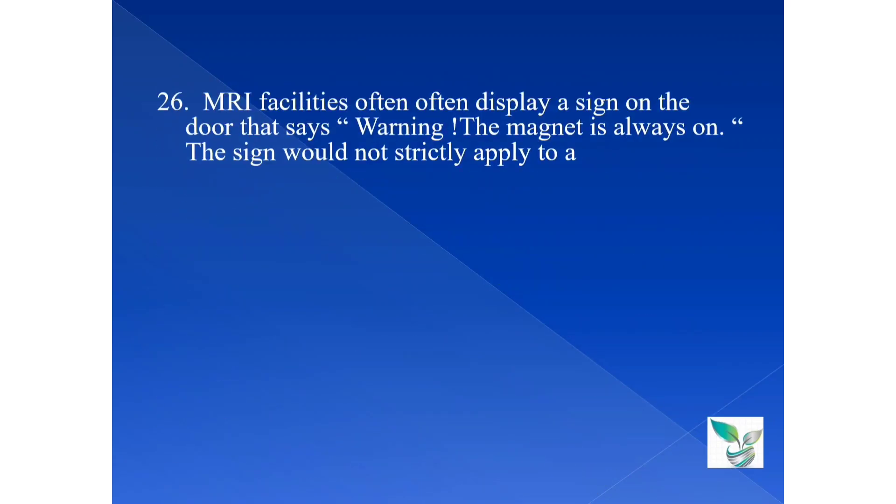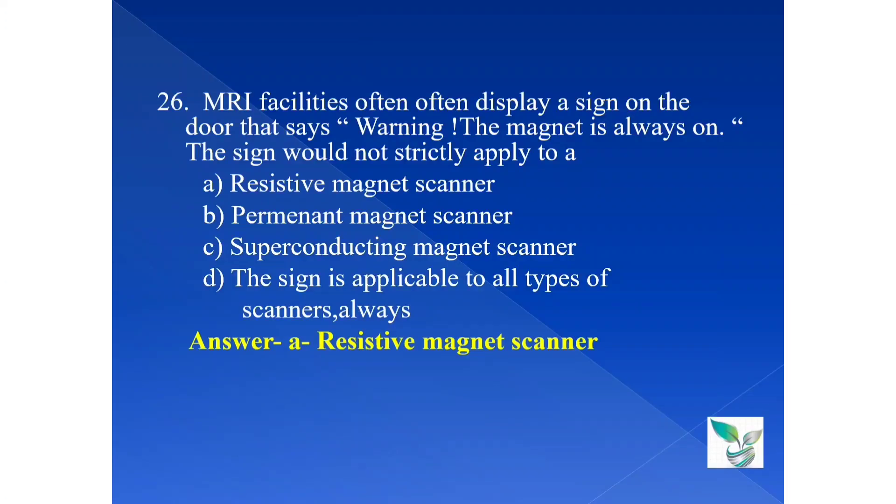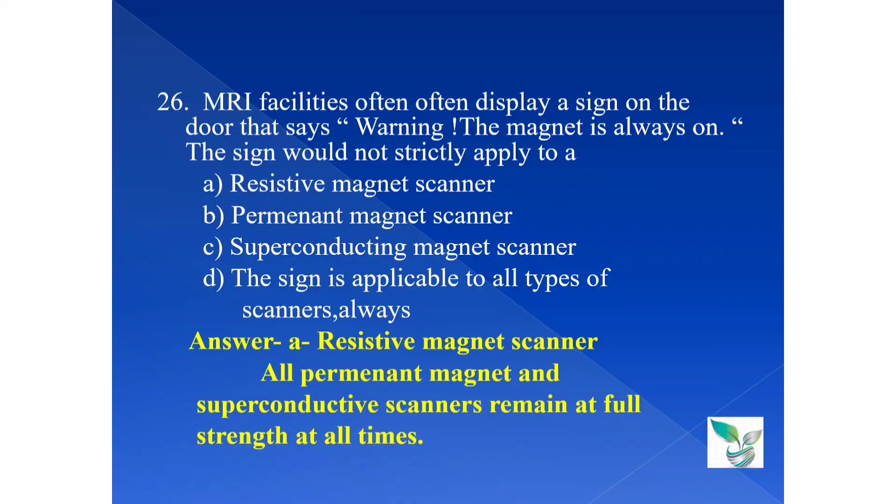Moving on to the next question, question number 26. MRI facility often display a sign on the door that says, Warning, the magnet is always on. So, the sign would not strictly apply to option A, resistive magnet scanner, option B, permanent magnet scanner, option C, superconducting magnet scanner, and option D, the sign is applicable to all type of scanners, always. The answer is option A, resistive magnet scanner. So, the sign which does not strictly apply to a resistive magnet scanner. Let's see the explanation. All permanent magnet and superconducting scanners remain at full strength at all times.